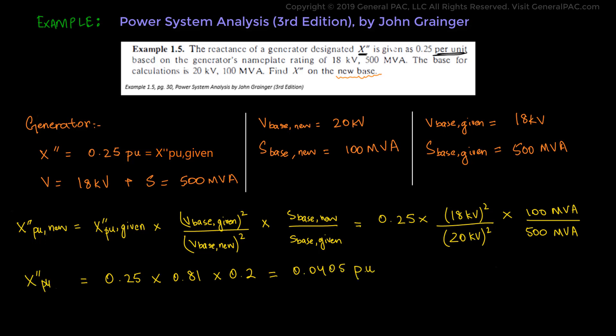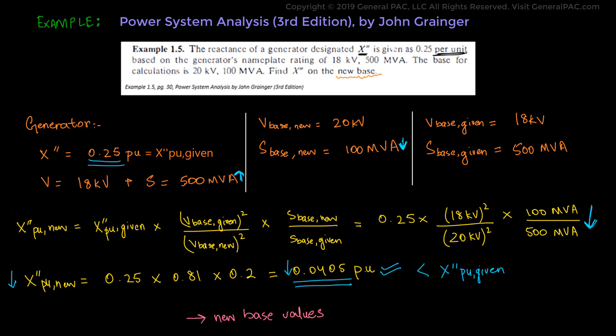So that is the value of the new per unit impedance. Comparing the new impedance value, we can clearly see that it is quite smaller than the previous one — 0.0405 per unit versus the original 0.25 per unit. This makes total sense because previously the 0.25 per unit impedance was calculated with a considerably larger MVA rating of 500 MVA. When we converted the impedance to a smaller MVA rating of 100 MVA, the effective impedance value decreased considerably. This method is employed everywhere where there is a need to calculate a new per unit value when base values have been changed, whether in simple or complex power system analysis.